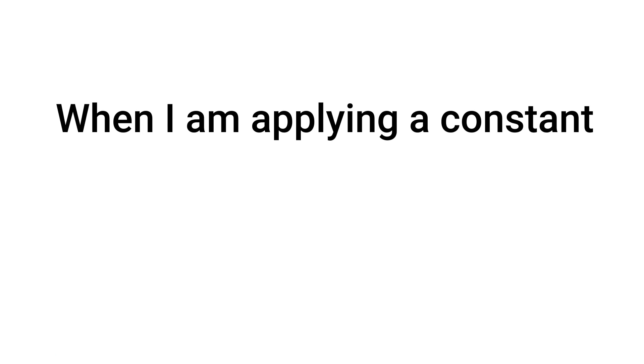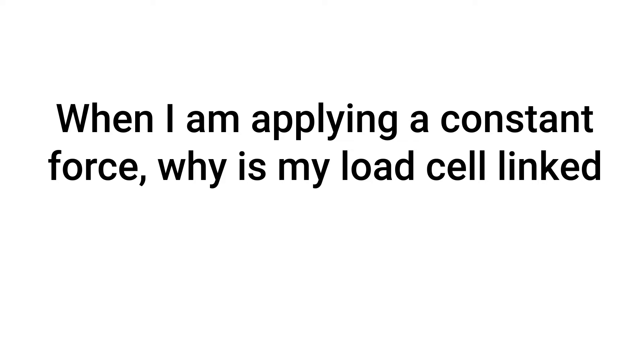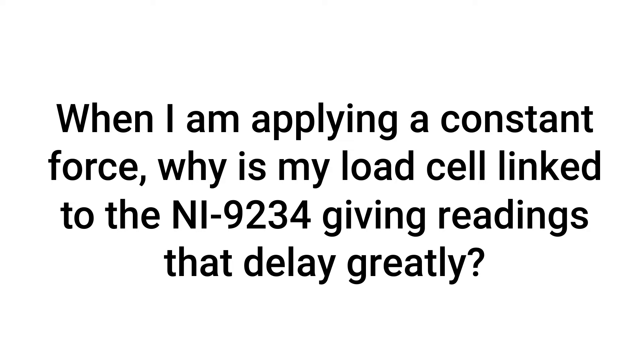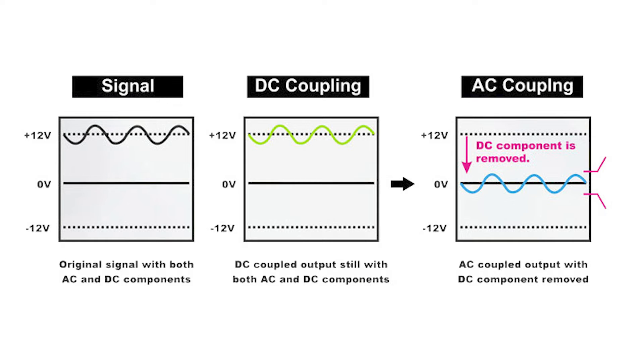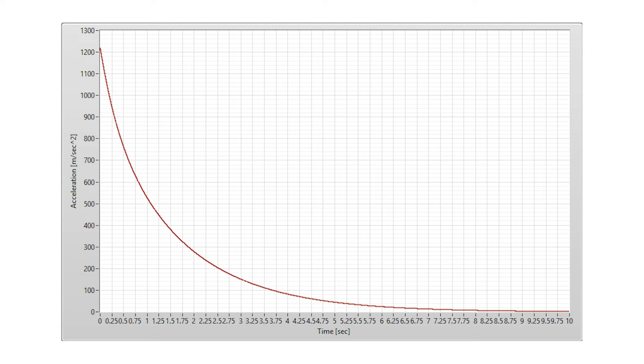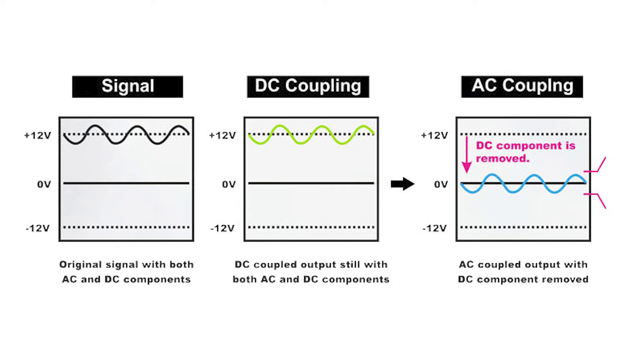When applying a constant force, why is my load cell linked to the NI9234 giving readings that delay greatly? This may be happening because numerous load cells and external power supplies have AC coupling circuitry, which is meant to discard DC noise from the external power supply. Sometimes this can cause the signal to decay exponentially. The choices are to either use sensors without AC coupling circuitry, or if external excitation is required, pick a power supply without AC coupling circuitry.